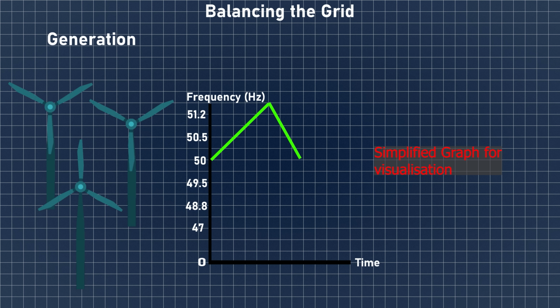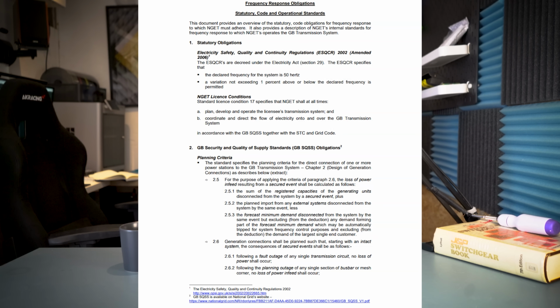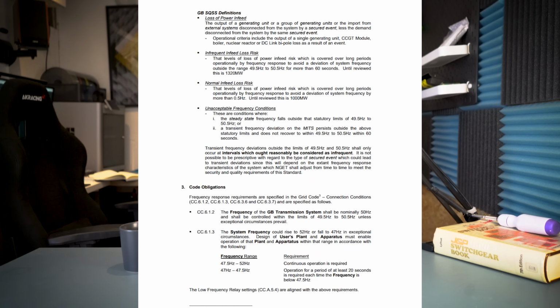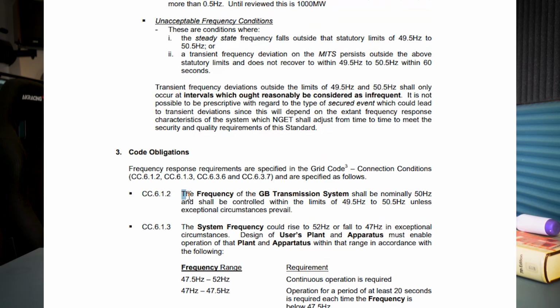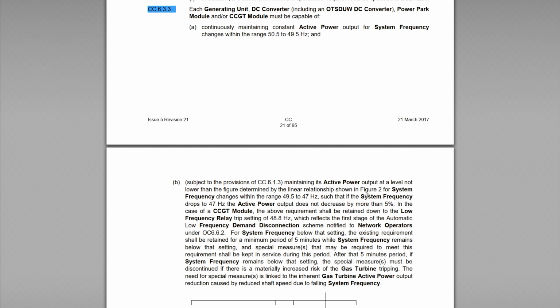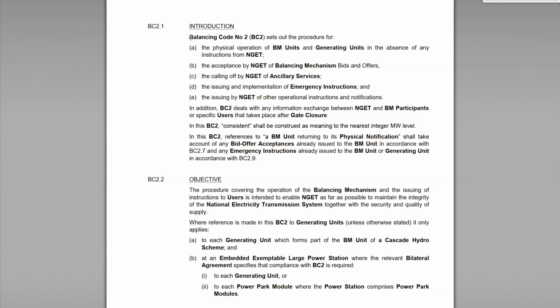In the UK, our frequency is set at 50 Hz, with a margin of 0.5 Hz either side, before the NESO must act to correct it. If it goes beyond that range, the NESO goes into alert, where it must use reserves to correct the frequency, and if it manages to go below 48.8 or above 51.2 Hz, we get into load shedding and low frequency trips, where generators are automatically disconnected to protect the system. This specification is set out in grid code, specifically Balancing Code 2 and Operational Code frequency limits, and that number is the cliff edge before we get widespread generator disconnection.